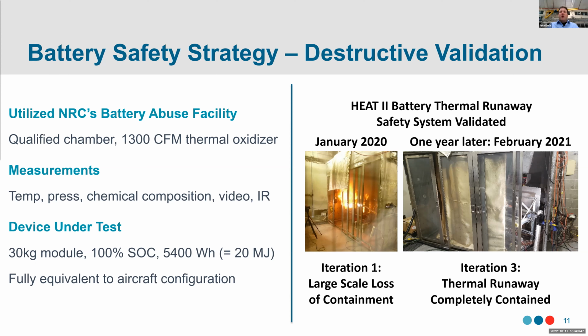In the second test, we were almost successful. It appeared to be containing until the insulation on one of the high voltage cables inside one of the modules melted away, allowing the high voltage cable to contact the casing. In essence, we created an 800-volt arc welder, which welded a hole through the top of the casing, allowing the gases and flames to exit. Finally, on our third attempt, about a year after our first bonfire, we were fully successful.